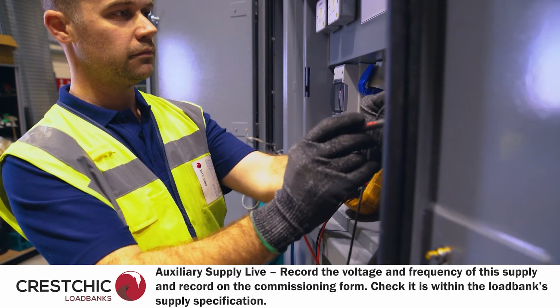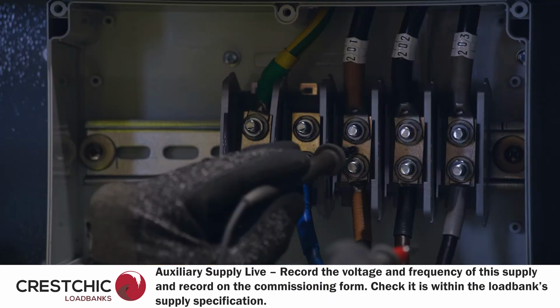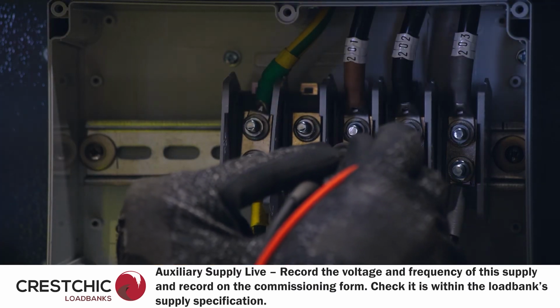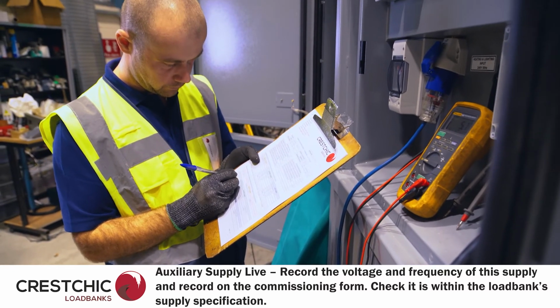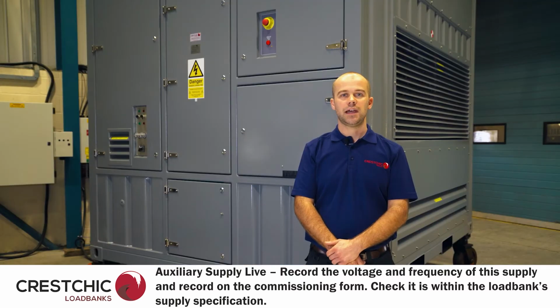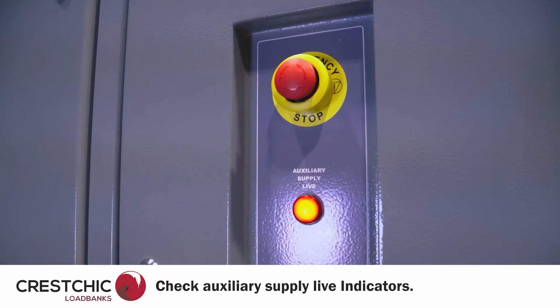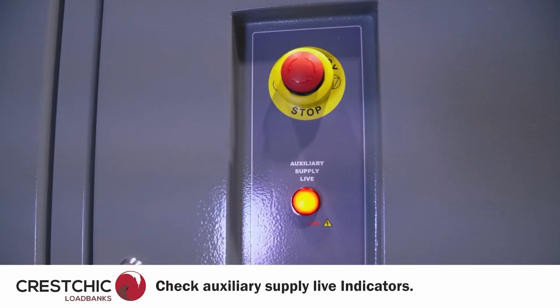The auxiliary supply can now be turned on. The voltage and frequency should be checked and recorded on the commissioning form. Now the auxiliary supply is live onto the load bank, various checks should be completed. These are as follows. Please note, not all may be applicable to your load bank. Check auxiliary supply live indicators.